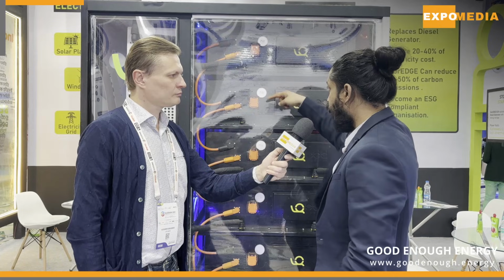This has five modules of 50 kilowatt each and a liquid thermal management technology which cools the battery every time. It has a PCS, a 125 kVA inverter system, and a liquid thermal management technology with a chiller to cool this. And we have another one which I'll show you right here.